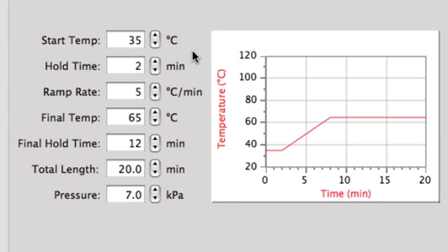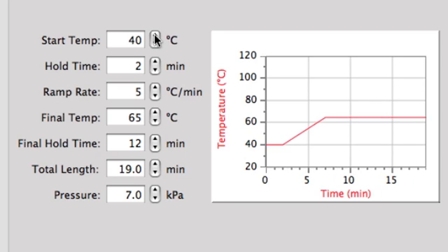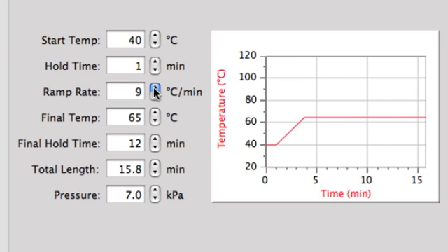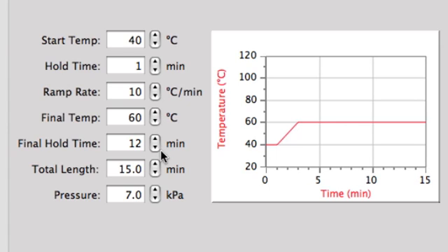For this experiment with my mixture of organic substances, I'm going to start the temperature at 40 degrees and hold that for one minute. I'm going to increase the ramp rate to 10 degrees C per minute and set the final temperature at 60 degrees C.